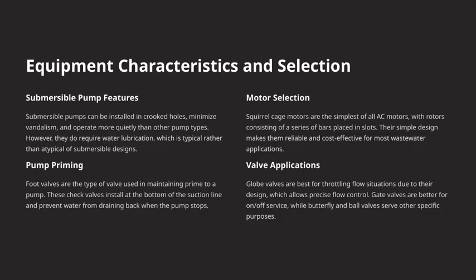Moving on to pump priming, this is a critical step to ensure the pump works efficiently. Foot valves are commonly used here. These check valves are installed at the bottom of the suction line and serve a vital purpose. They help maintain the prime by preventing water from draining back when the pump stops. This means the pump can restart quickly and operate smoothly without needing to be reprimed each time.